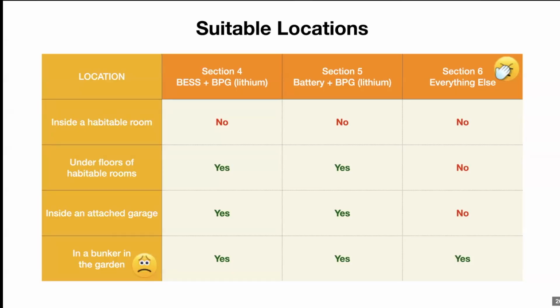Okay, so here's a little summary about where under this standard you can install a battery system or a BESS. Now, remember I said section 4 only applies to lithium batteries that are pre-assembled BESSes and comply to the best practice guide. So BPG is best practice guide. You'll see that inside a habitable room is no for all types, all categories of batteries. Can they be installed under the floors of habitable rooms? Yes, for sections 4 and 5, but no for section 6. Now, I haven't explained sections 5 and 6 yet.